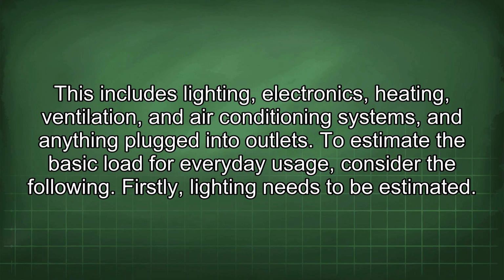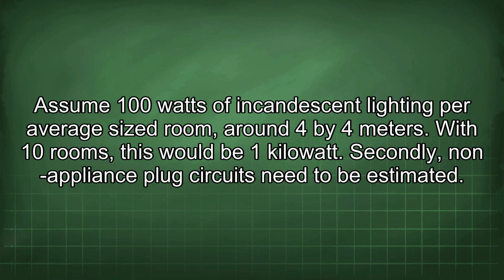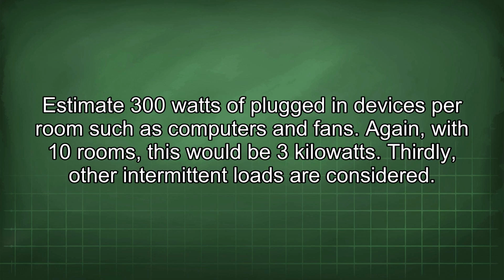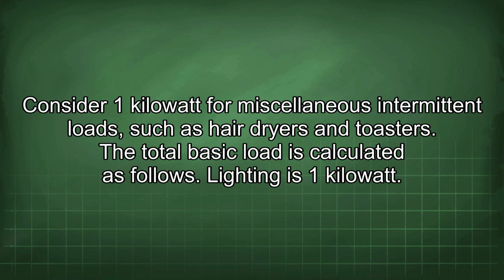To estimate the basic load for everyday usage, consider the following. Firstly, lighting needs to be estimated. Assume 100 watts of incandescent lighting per average sized room, around 4 by 4 meters. With 10 rooms, this would be 1 kilowatt. Secondly, non-appliance plug circuits need to be estimated. Estimate 300 watts of plugged-in devices per room, such as computers and fans. Again, with 10 rooms, this would be 3 kilowatts. Thirdly, other intermittent loads are considered. Consider 1 kilowatt for miscellaneous intermittent loads, such as hair dryers and toasters.